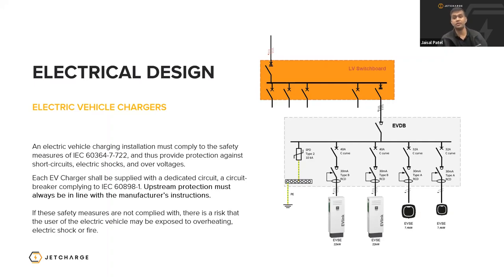And this is a very important point: upstream protection must always be in line with the manufacturer's instructions. So before you specify any charger, please read through the manufacturer's instructions on what they recommend is the best form of protection for that charger. Because if these safety measures are not complied with, there's a risk that the user will be exposed to overheating, electric shock, or fire. Next slide, please.